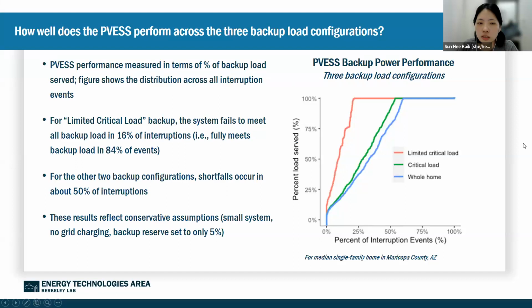Our first analysis looks at the backup performance of the solar+storage system for all simulated power interruptions across three load configurations. The system successfully served the entire limited critical load for 82% of simulated events. For the entire critical loads, 52% of events were covered, and for whole buildings, only 43% of the simulated events were covered.